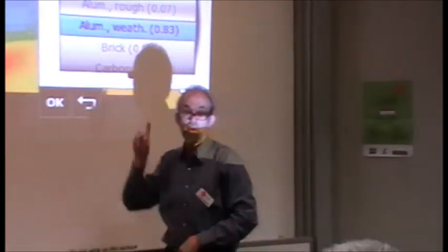If I look at that there, they have an emissivity table you can look up. That's all gone. That's going to help me, isn't it? Oh, yes, most definitely. Okay, we look at aluminium. First of all, they haven't got smooth aluminium, but they have got a clean, and they're saying down to 0.07, so even lower than what I was guessing there. But they're calling it rough.